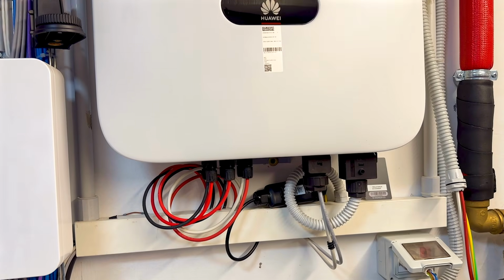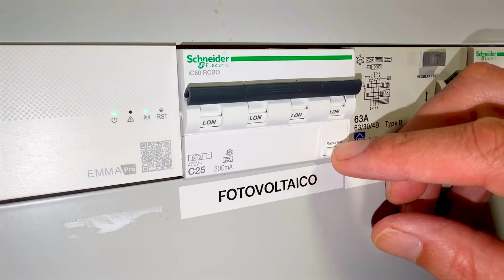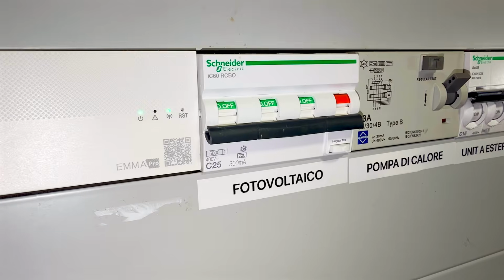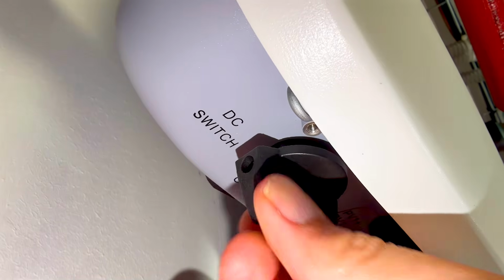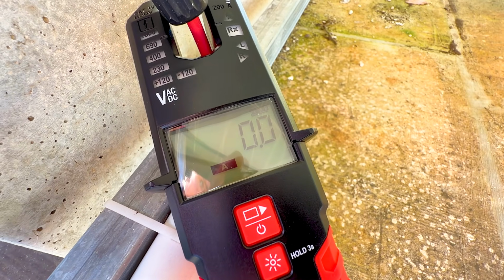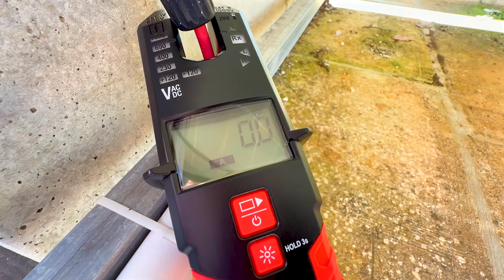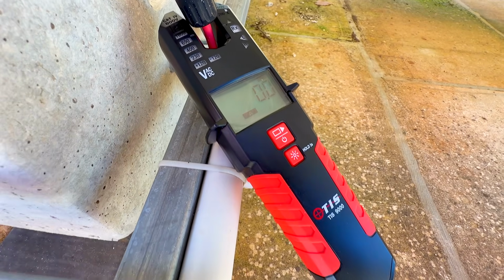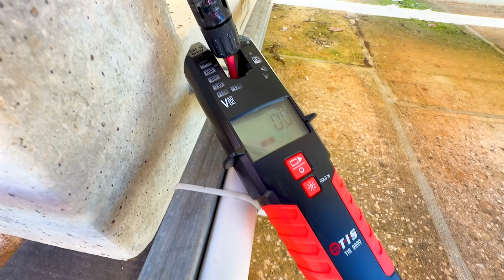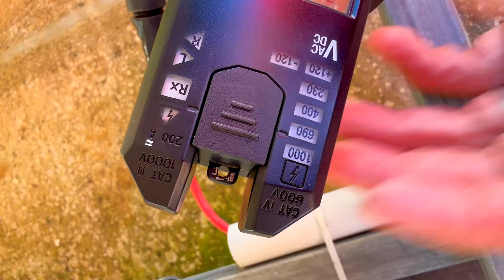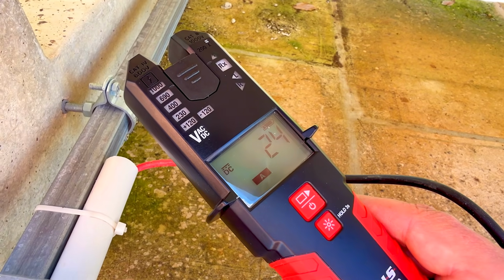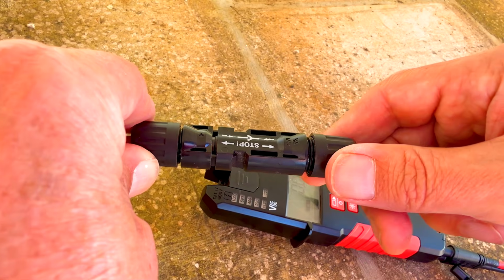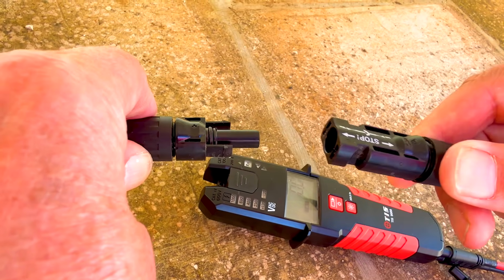So before we go anywhere near that connector, I'll shut the system down properly. First the AC side, then the inverter's built-in DC isolator. And now you can see that current has dropped to 0, but we don't just trust the number on the screen. Just like proving a voltage indicator, we can check the tester is behaving itself using this proving magnet, confirming it's reading correctly before and after the test. So now we can disconnect the MC4 connector without the risk of drawing an arc.